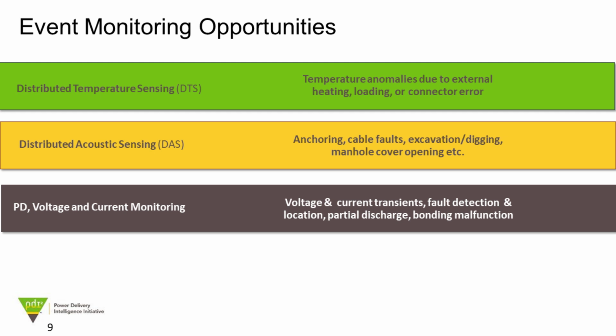So monitoring temperature, looking for hotspots along cable system, acoustic sensing, looking, for example, for third-party intrusion. I remember this ICC presentation from a US utility who said that they had no cable system failure in their network related to, let's say, quality issues, but they had many failures related to excavation. So obviously we were in very busy American cities and people building buildings, digging and pulling cables when they were not aware that cables were there.